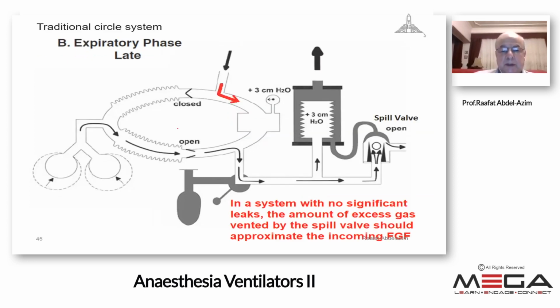This is the expiration in which the patient's lung will be deflated. The contents will come through the expiratory limb, expiratory valve into the bellows. It will ascend up, it will be completely inflated, and the excess gas will go to the spill valve to be vented into the scavenging system.